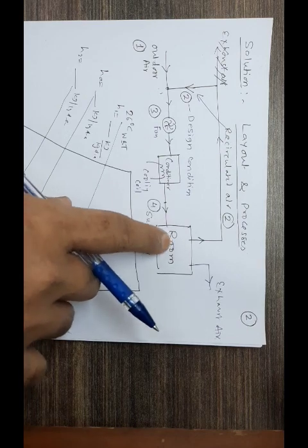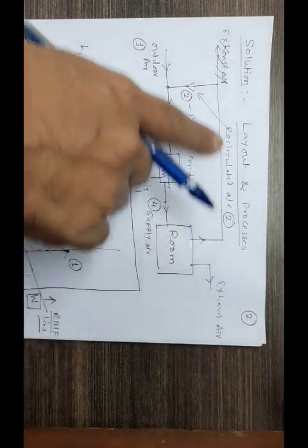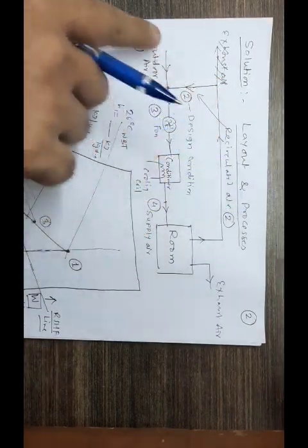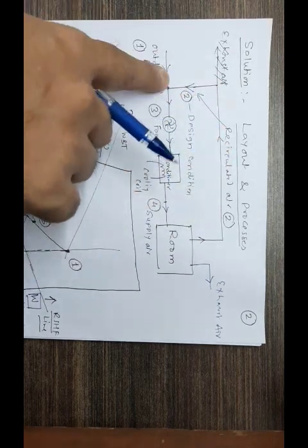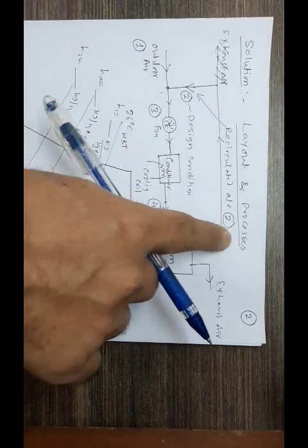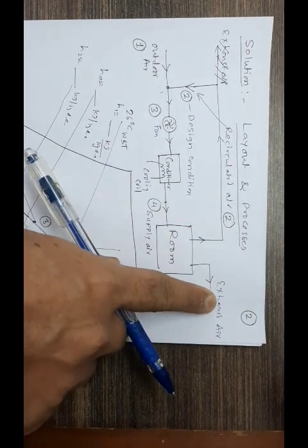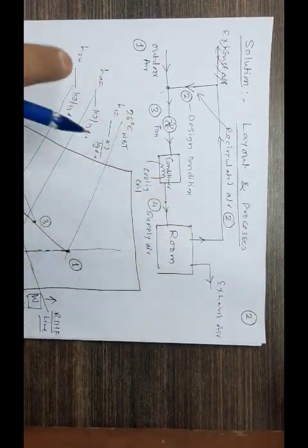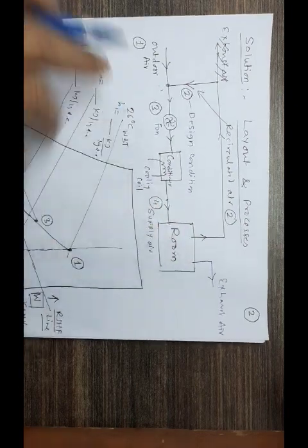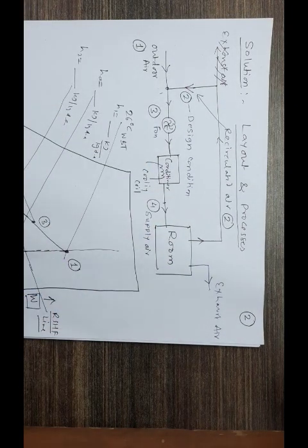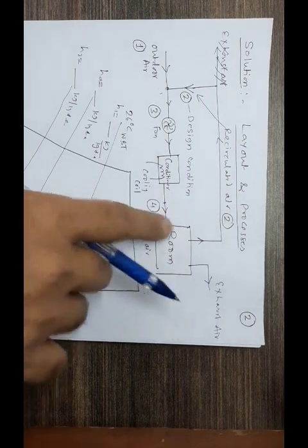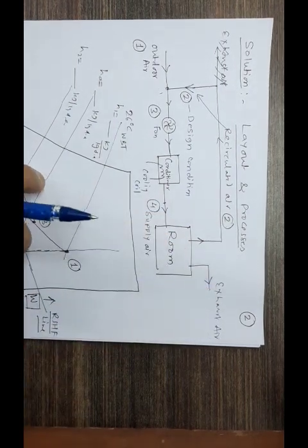Ultimately from here you take back 60% of it. This is 40, this is 60, 40 plus 60 is 100. So if you're taking 60 out of this here, the remaining 40 also should be exhausted. Only then will the mass be balanced, otherwise pressure will start rising here, because it's just pumping outdoor air into the conditioned space. Definitely the pressure inside will go on rising. So there is exhaust obviously.